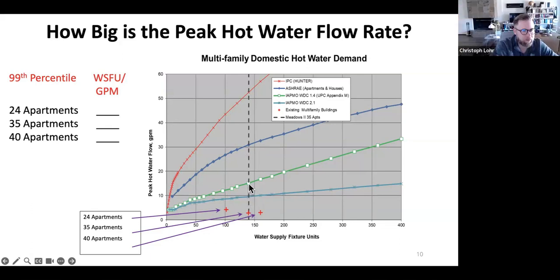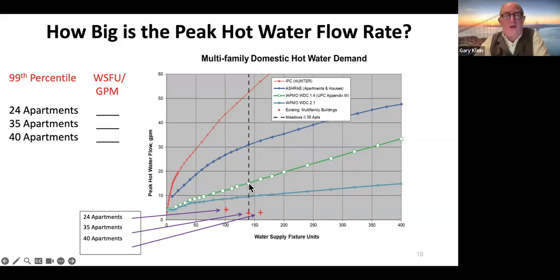Yeah. And so we were using version one, and we predicted 16 gallons a minute instead of 52 gallons a minute on the hot side. We never measured more than 3 gallons per minute in that apartment building. The whole building, that's the whole shooting match, not just one apartment. The huge, huge difference. And so we felt comfortable that we could actually do some right-sizing work here, and we were able to take a 3-inch main for that building down to a 1.5-inch main based on version one.